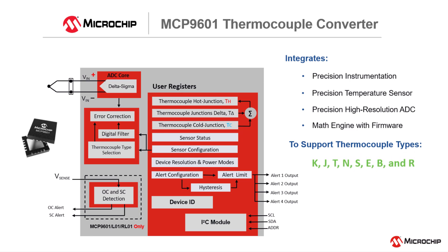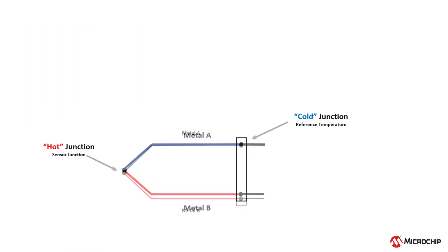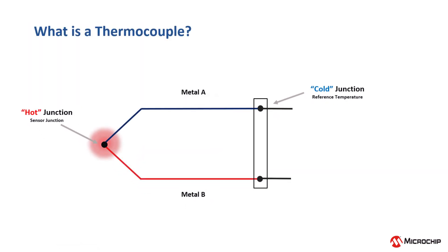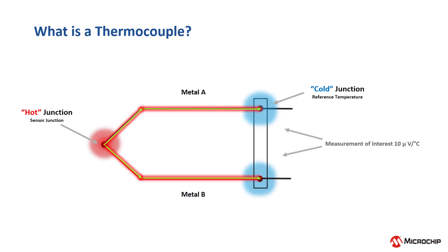To start, I will give a brief overview of what a thermocouple is. A thermocouple consists of two dissimilar wires joined at one end. The joint end is called the hot junction and is the temperature that is being measured, and the open end is the cold junction. The voltage potential is proportional to the temperature and is known as the Seebeck effect. The voltage change is in the range of tens of microvolts per degree Celsius. This requires precision instrumentation to accurately calculate the corresponding temperature at the hot junction.